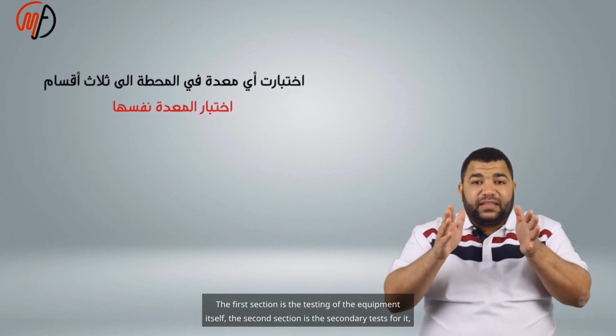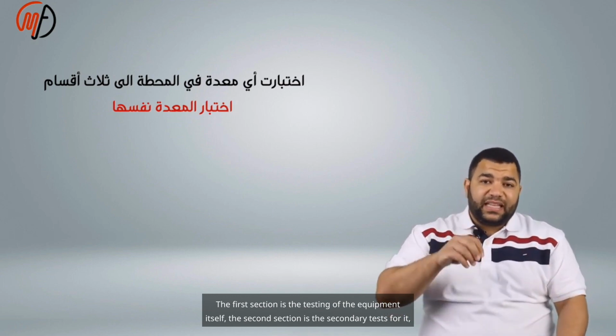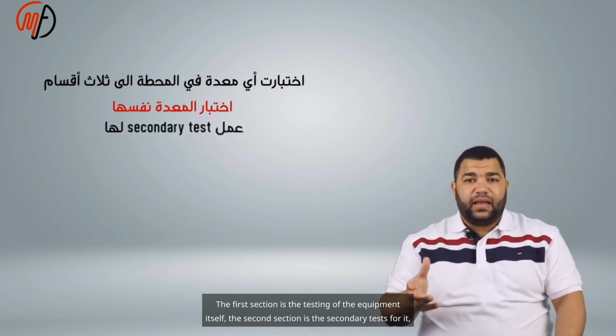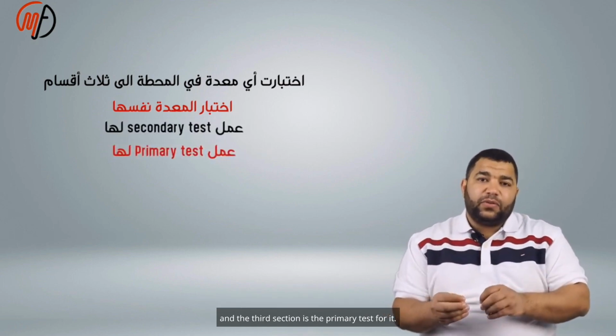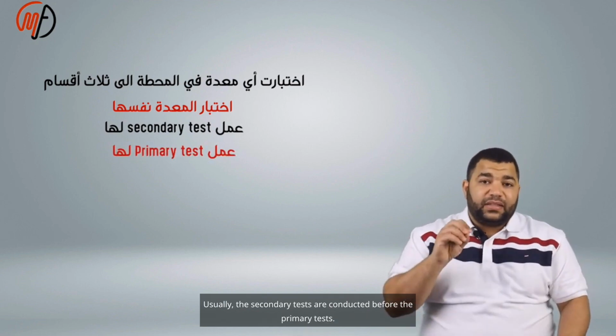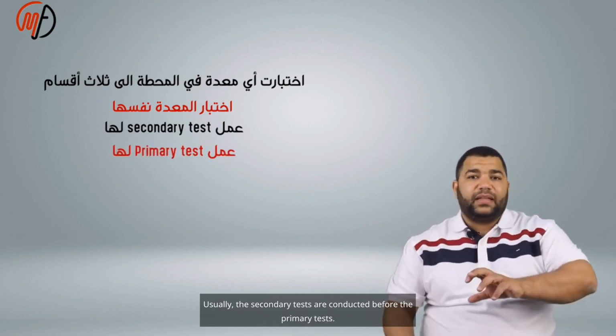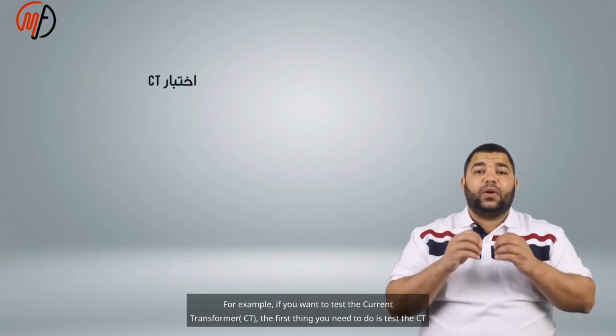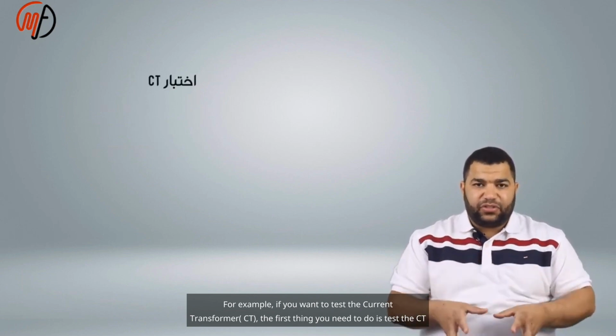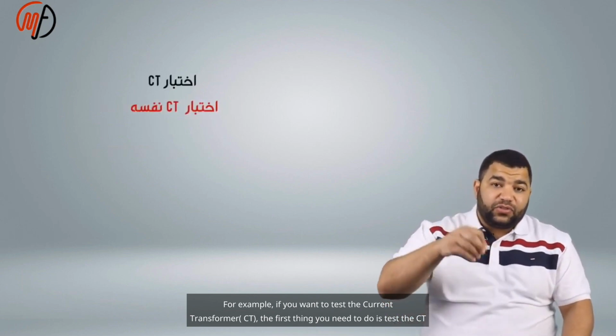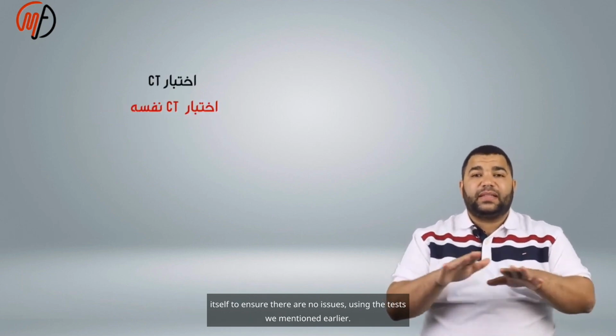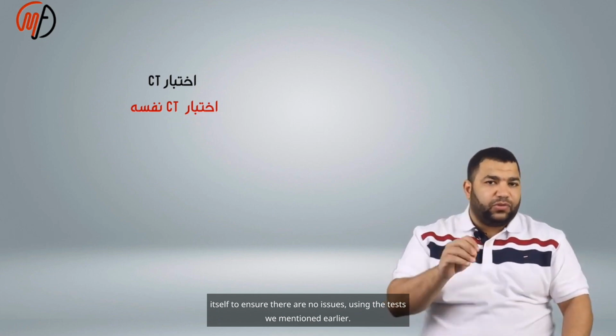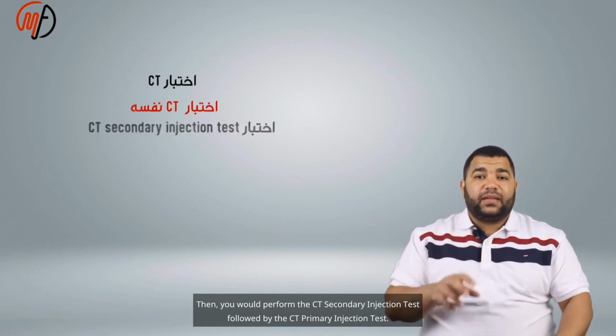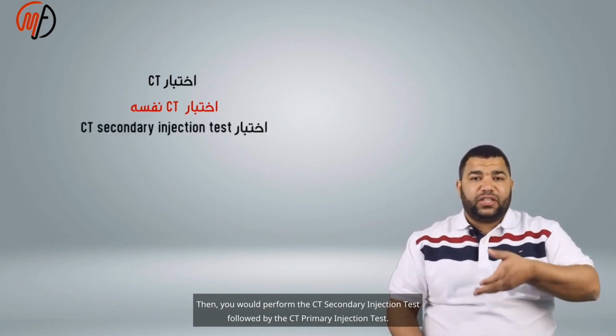The first section is the testing of the equipment itself, the second section is the secondary tests for it, and the third section is the primary test for it. Usually, secondary tests are conducted before the primary test. For example, if you want to test the current transformer, CT, the first thing you need to do is test the CT itself to ensure there are no issues, using the test we mentioned earlier. Then you would perform the CT secondary injection test, followed by the CT primary injection test.